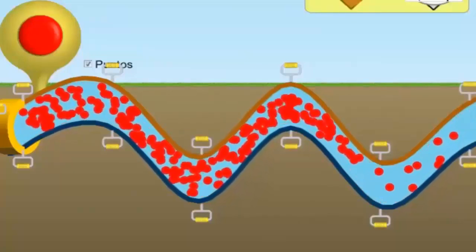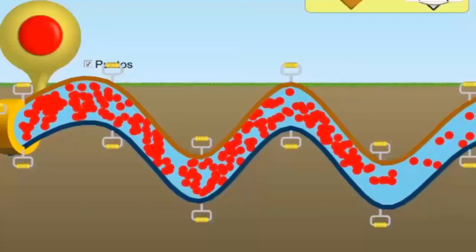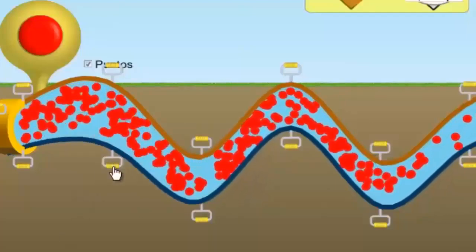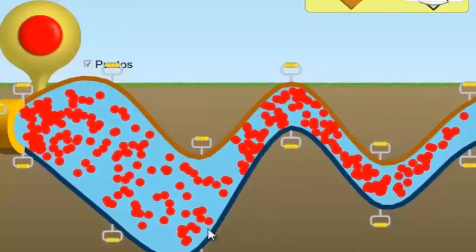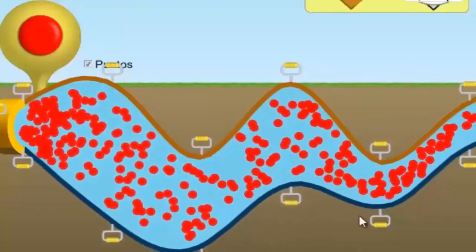Tenth, as the length of the capillary tube decreases, the flow slowly increases until the critical point is reached, where the flow rate increases more rapidly with each reduction in length.